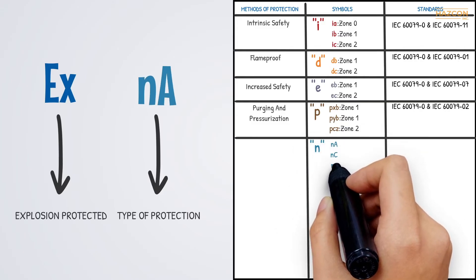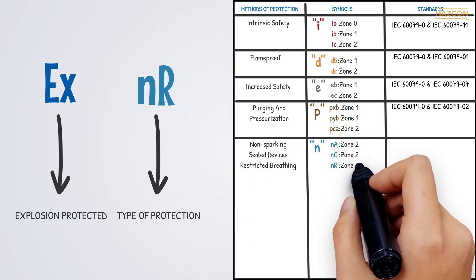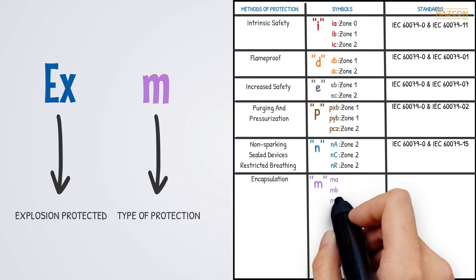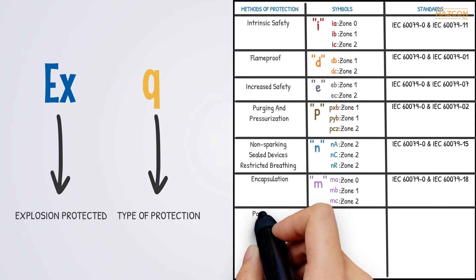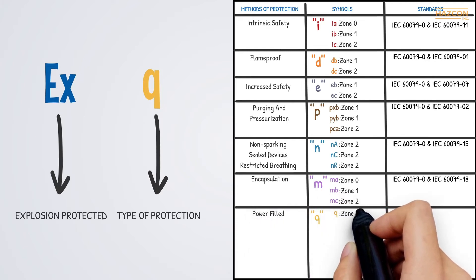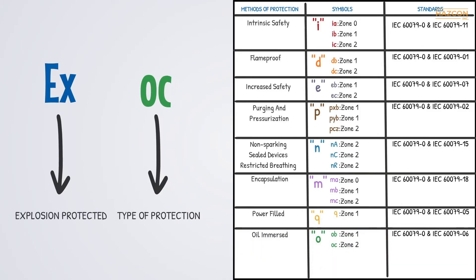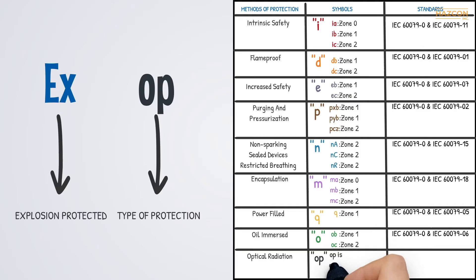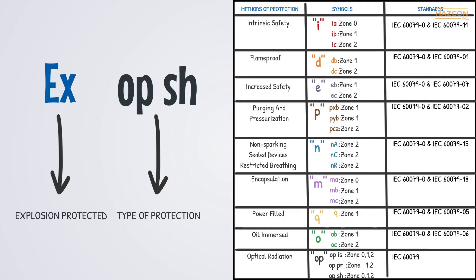N generally means non-arcing. NA is known as non-sparking, NC is known as sealing, and NR refers to a restricted breathing enclosure. M means that encapsulation is used as the protection technique. There are MA for Zone 0, MB for Zone 1, and MC for Zone 2. Q is for powder-filled equipment and allows a product to be installed in Zone 1. O means oil-immersed equipment — OB for Zone 1 and OC for Zone 2. Last but not least is the protection technique for gases known as OP, which is used for equipment having optical radiation. There are OPIS for Zones 0, 1, and 2; OP PR for Zones 1 and 2; and OPSH for Zones 0, 1, and 2.